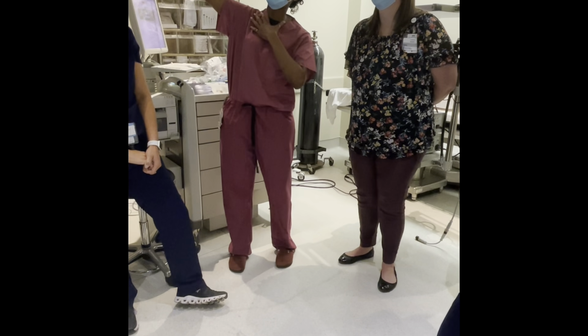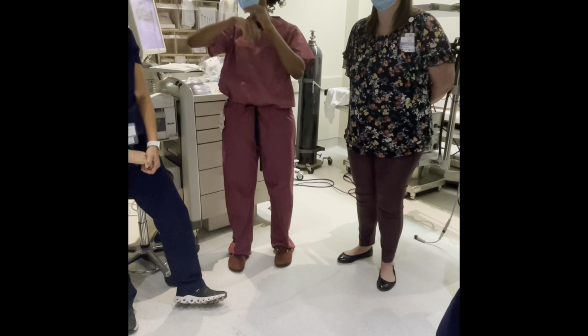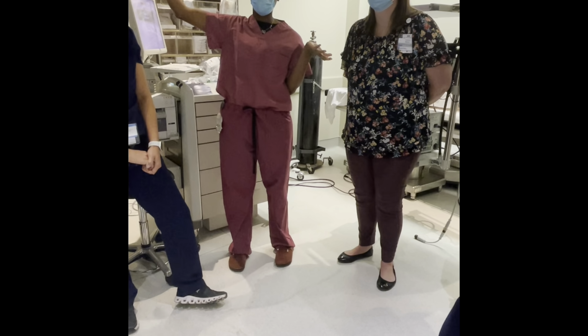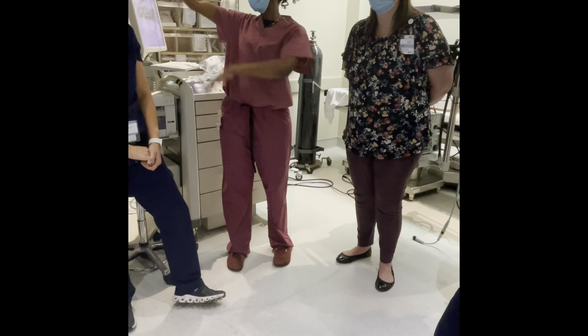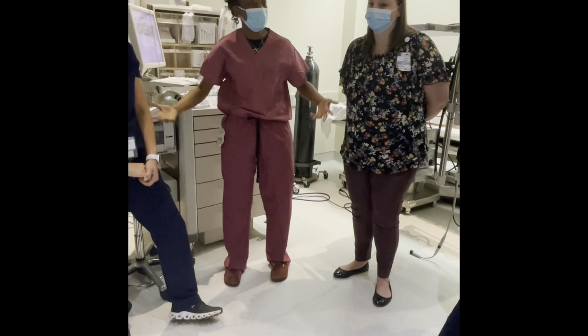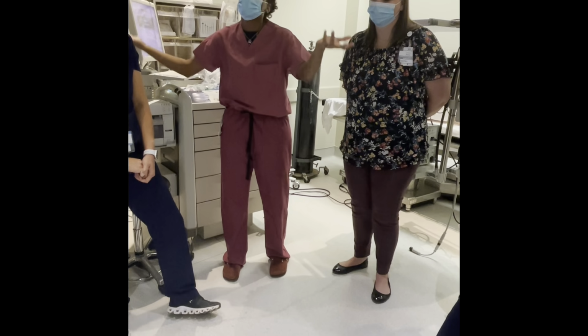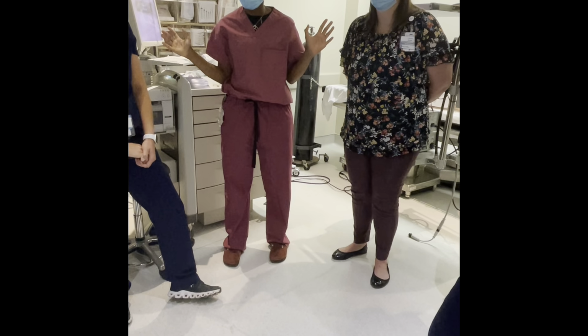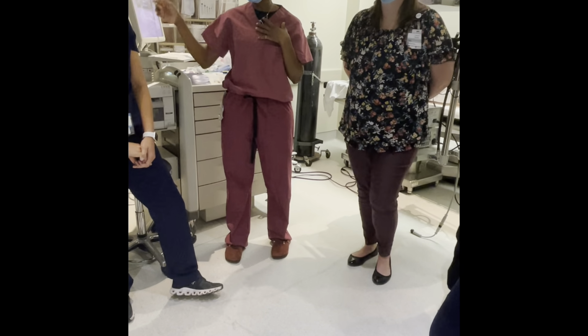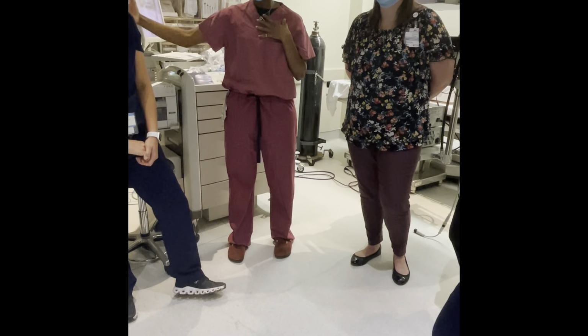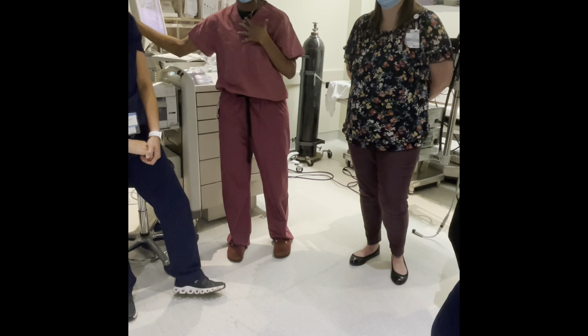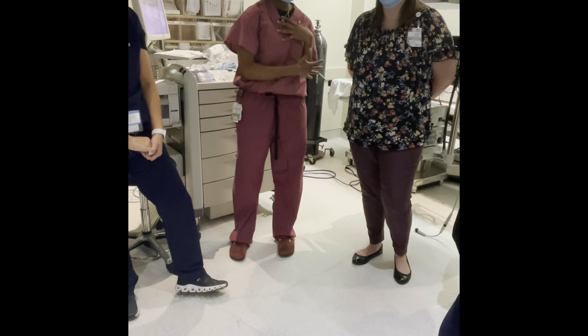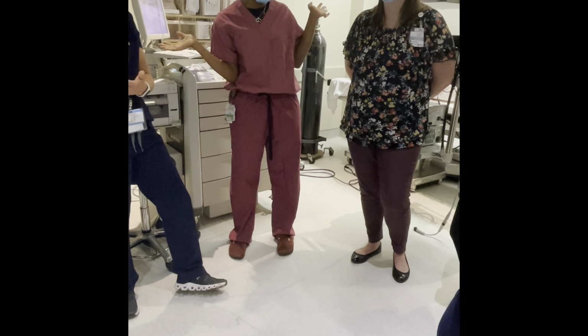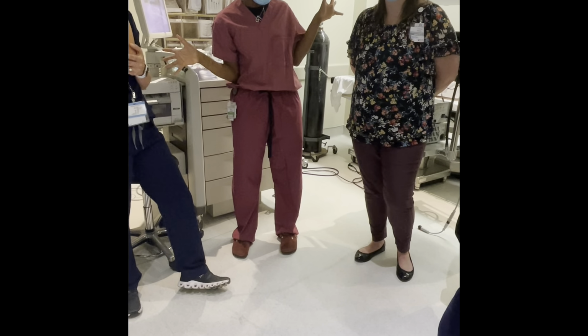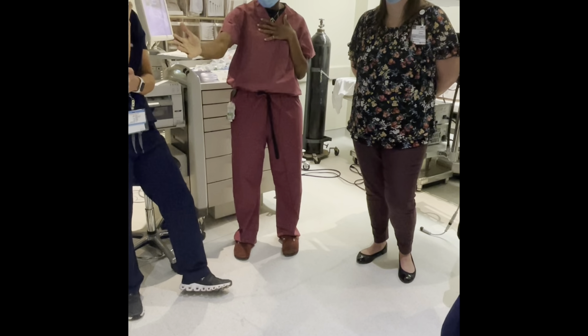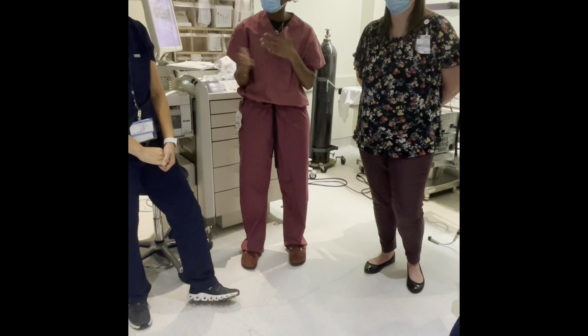Say you lose pipeline pressure, right? For whatever reason, say that got disconnected, somehow, or back wherever we store all the oxygen, I don't know where it stores it. Something got disconnected by someone. You will not know if the oxygen is left open, because the machine will then switch and pull oxygen from the cylinder in the back of the machine, right? Because it's gonna get it wherever it can until it doesn't have anymore. Then the alarm will go off to tell you, oh, there's no oxygen.